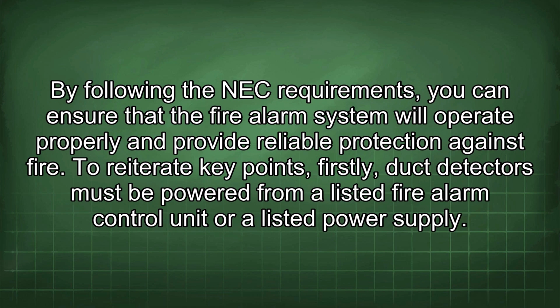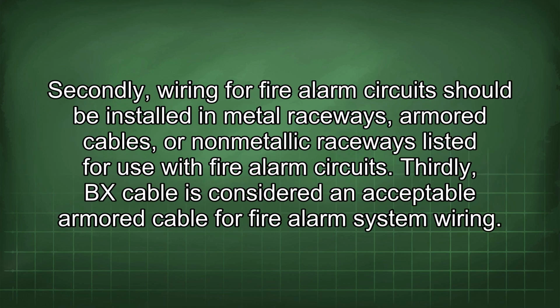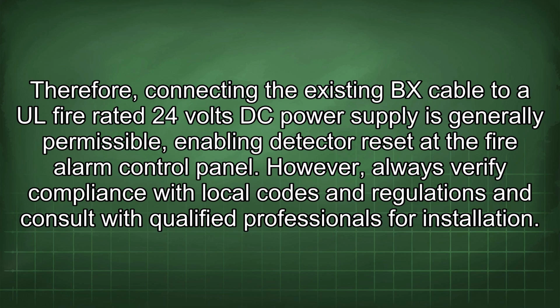To reiterate key points: firstly, duct detectors must be powered from a listed fire alarm control unit or a listed power supply. Secondly, wiring for fire alarm circuits should be installed in metal raceways, armored cables, or non-metallic raceways listed for use with fire alarm circuits. Thirdly, BX cable is considered an acceptable armored cable for fire alarm system wiring. Therefore, connecting the existing BX cable to a UL fire rated 24 volts DC power supply is generally permissible, enabling detector reset at the fire alarm control panel.